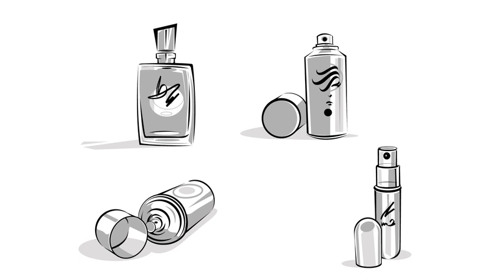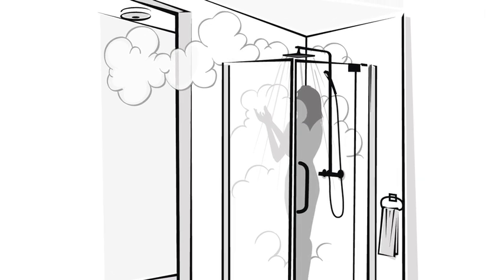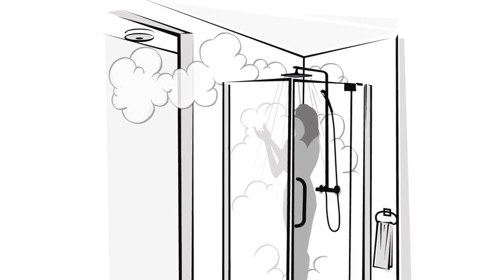Unfortunately, other phenomena can cause the very same effect as smoke, and this is where false alarms become a serious concern as they can cause nuisance, disruption and, worst of all, apathy as to the true validation of the alarm condition. Nuisance alarms from aerosols including deodorants, hair sprays and air fresheners, dust and steam from bathrooms and showers can all create the effects required to make the smoke detector alarm.